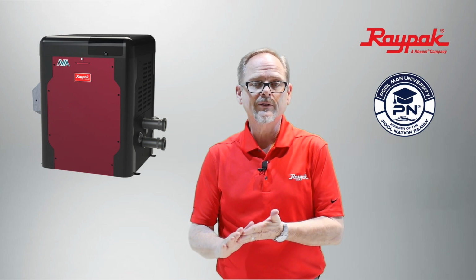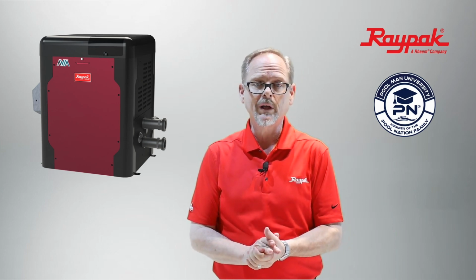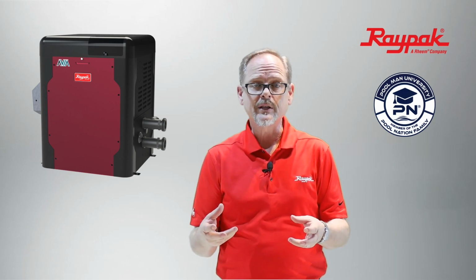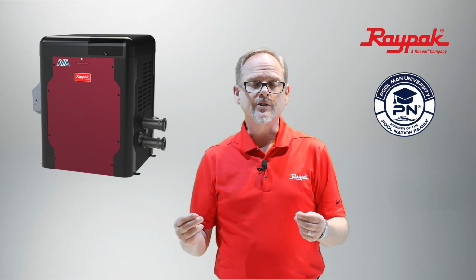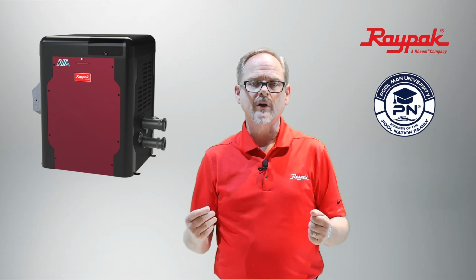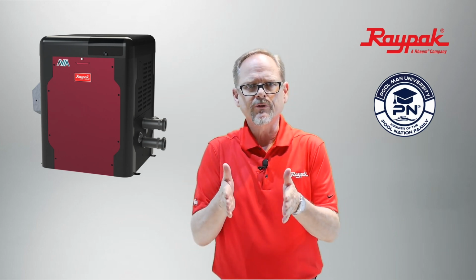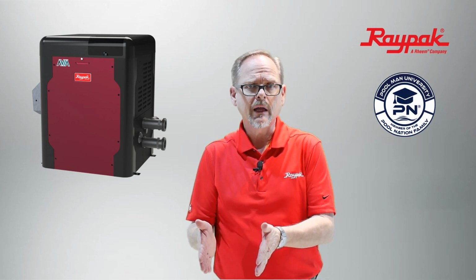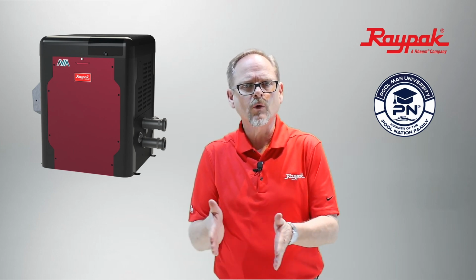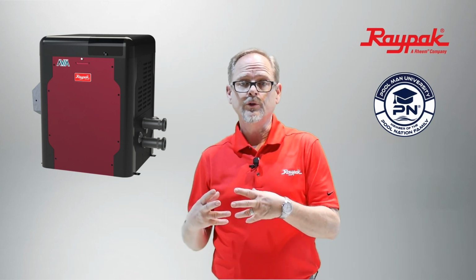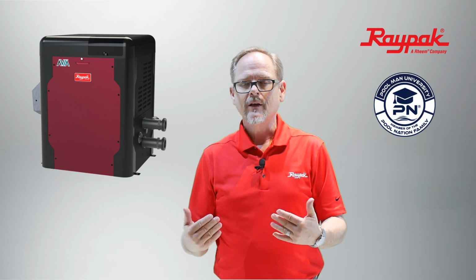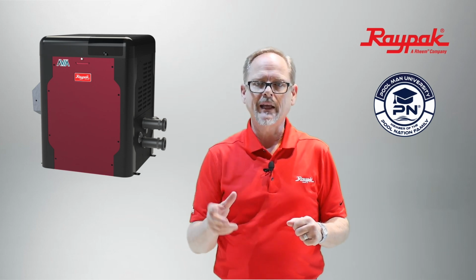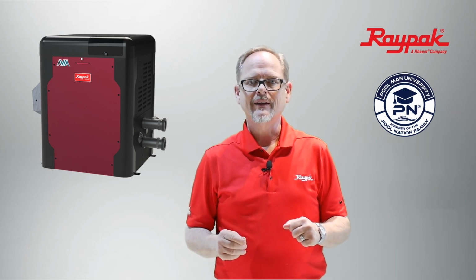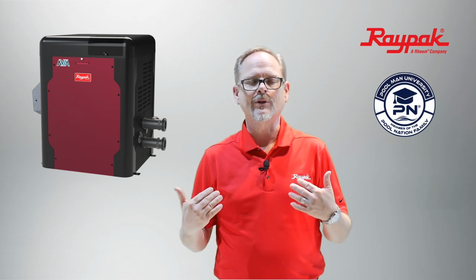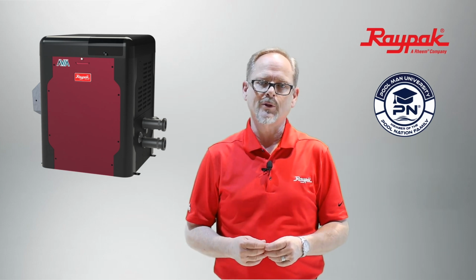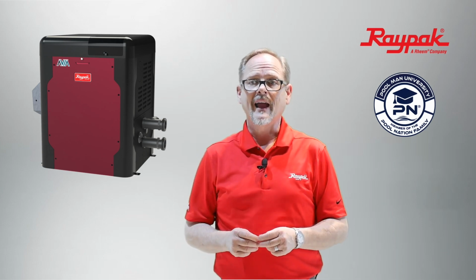The Protect Shield is another device that's available on any residential size Raypak swimming pool heater. This is a built-in standard piece of equipment that helps to mitigate the effects of damage due to ionic migration within the swimming pool itself. I mean, typically what you might find is anytime you put two different metals in water, any water, you create a battery. You create a small amount of DC voltage flowing back and forth between these two metals. And the less noble of the two metals will deteriorate at a faster rate. This is called the sacrificial anode. What if we put an anode in it from the start, from the factory, that is even lower on the nobility scale than what you might commonly find in a swimming pool? And this is what we've done with the Protect Shield. This comes standard on both the Avia and the digital.